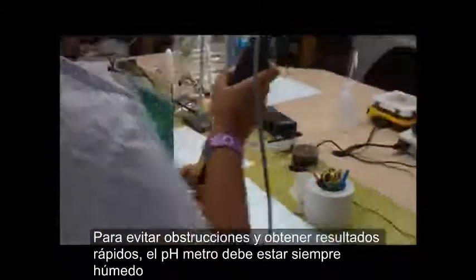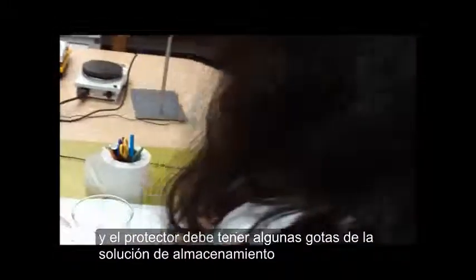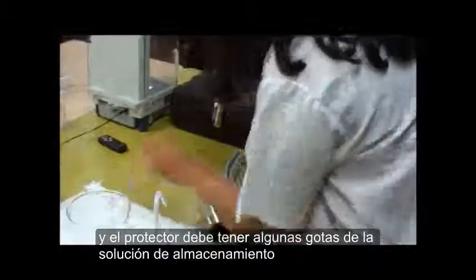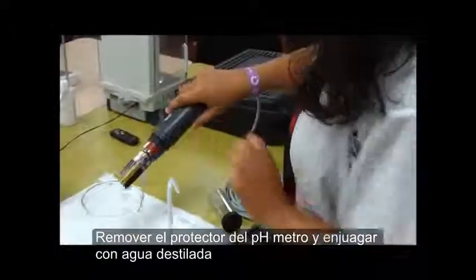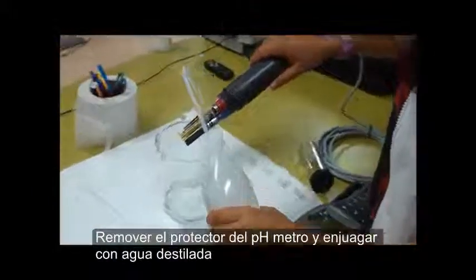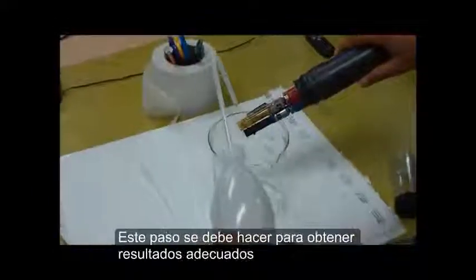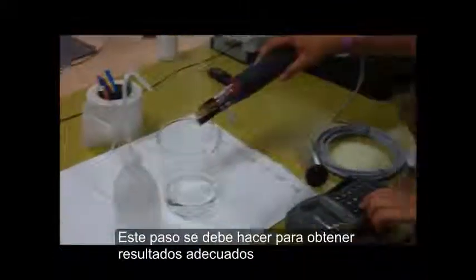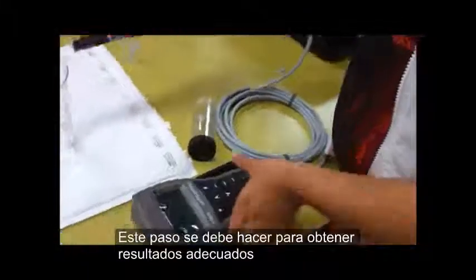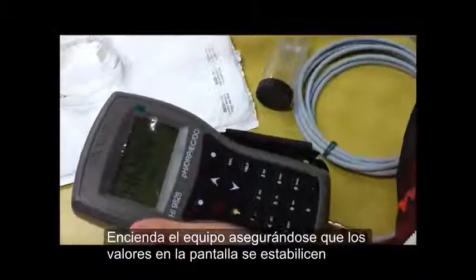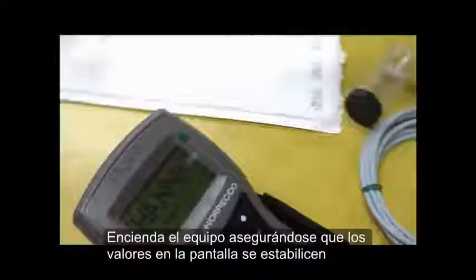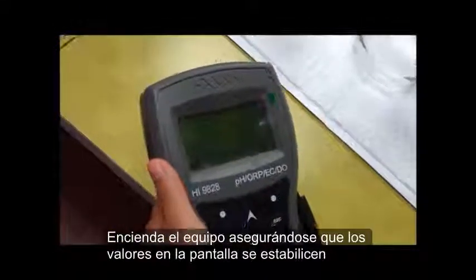The pH bulb must be kept moist at any time. Store the electrode with a few drops of storage solution in the protective cap. Remove the protective cap and rinse the pH sensor thoroughly with distilled water. This step must be done to neutralize the multiparameter for accurate readings. Turn the multiparameter on. Make sure that the readings on the screen are somewhat stable.